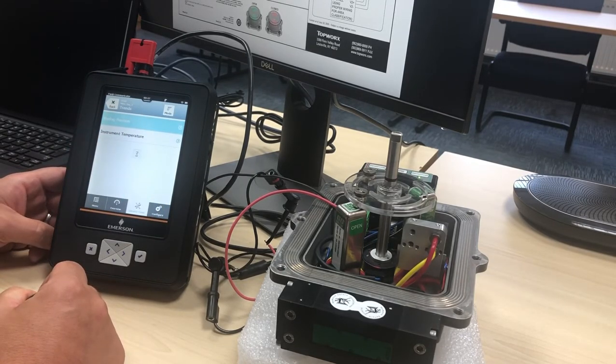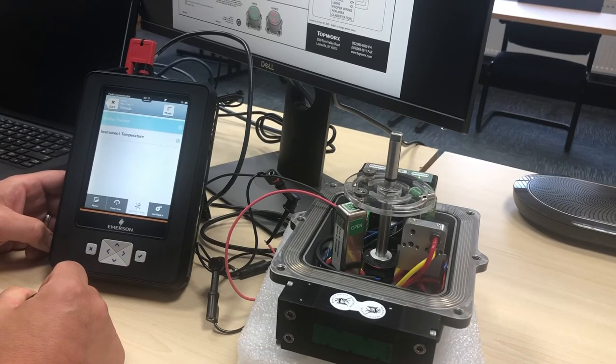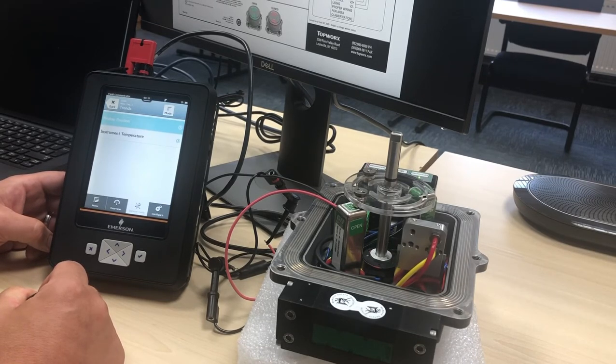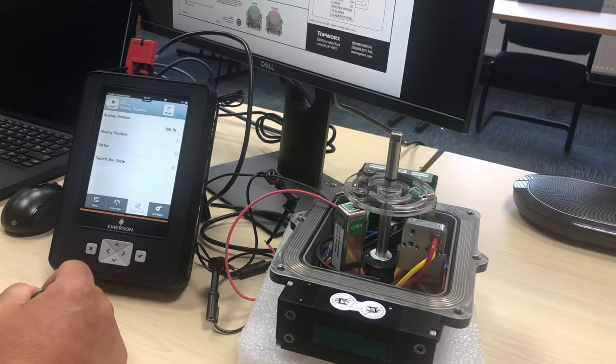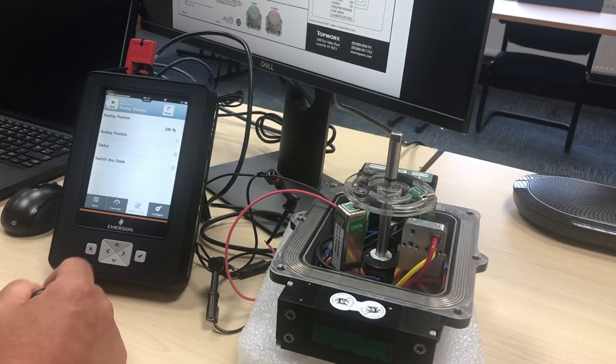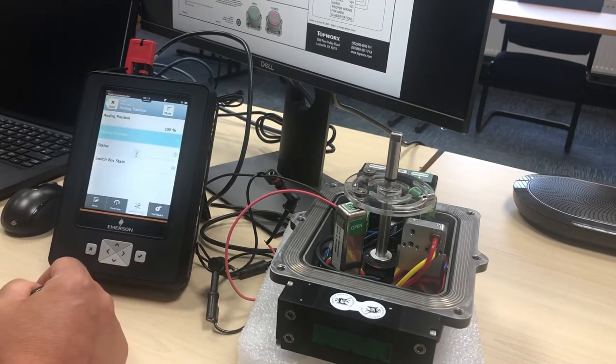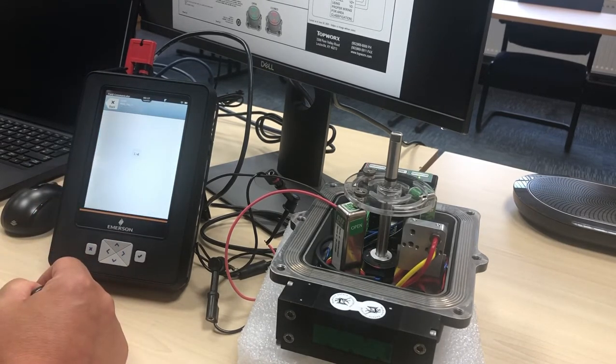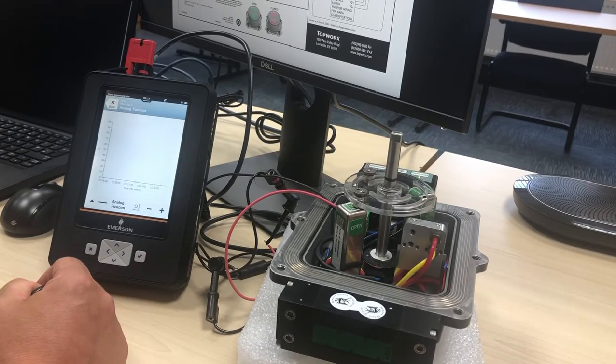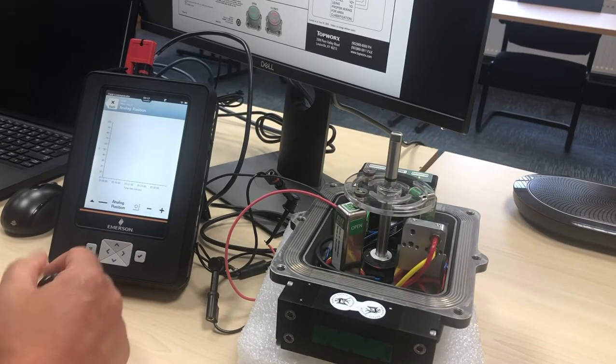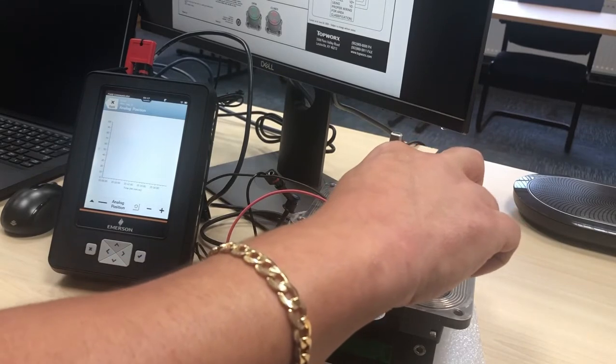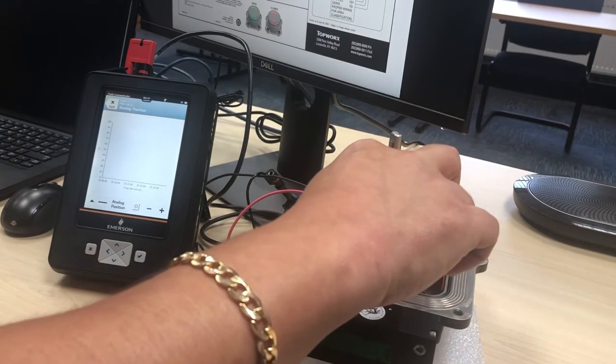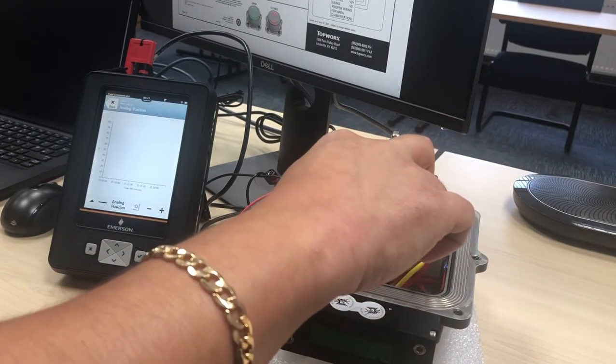With an Emerson Trex, what we're looking at now is the analog position, and this is a trend. What we're able to do is actually have a look at positions within the device and make a footprint of how it's actually operating in terms of the timing when it's opening and when it's closing.